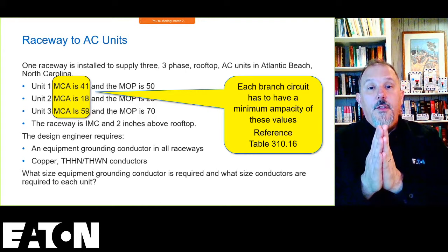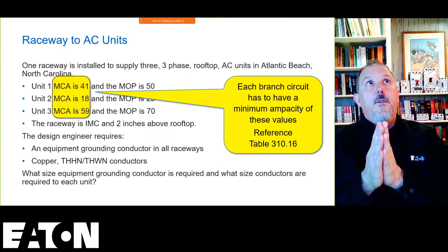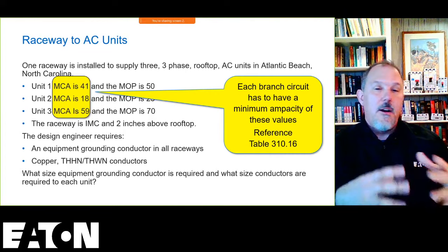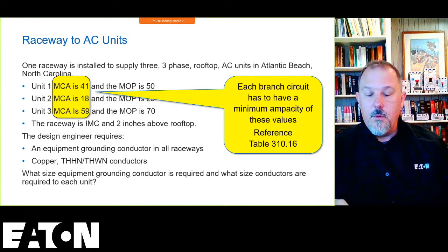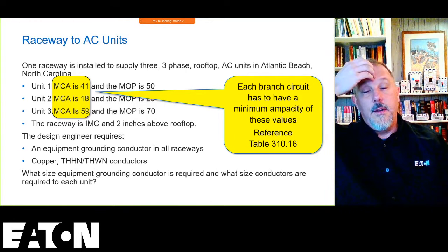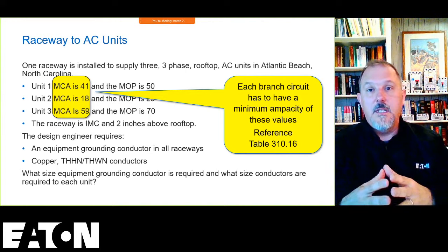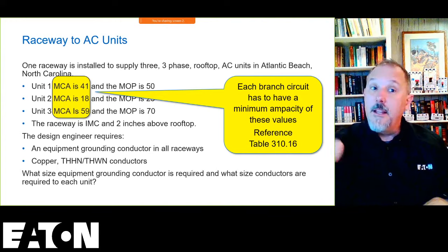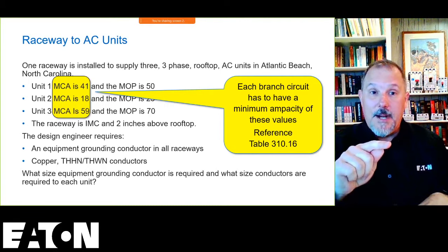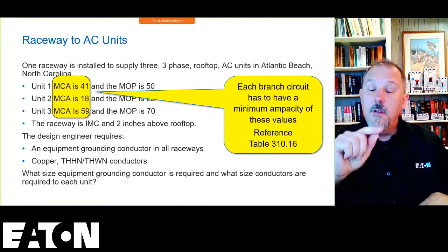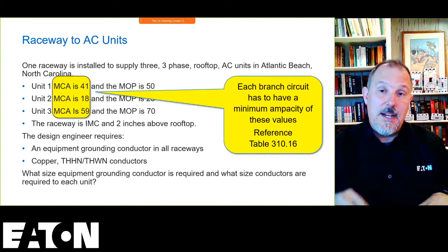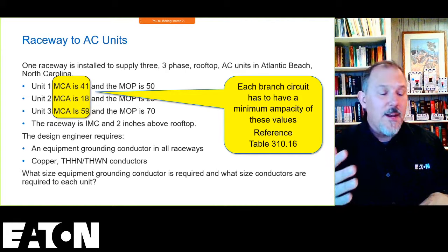Now, when you have a piece of equipment that is listed and it's marked with a minimum circuit ampacity, it's doing a lot of the details that you find in 440, all the different parts and pieces that are inside that one listed product. They're telling you that's all you have to worry about. You have to make sure that your conductors, based upon the conditions of use, can handle 41, 18, and 59 amps.